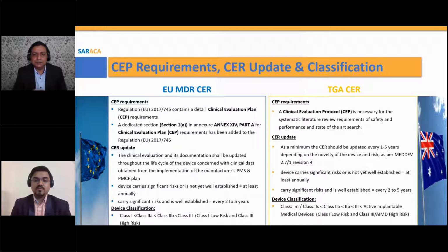Over to you, Sam. Yeah, I'd like to just follow up a little bit on risk. As I said earlier, risk is making its way into everything. And the risk analysis that you do for your device is to be included in the technical documentation, whether it be here in the United States, in the EU, in the TGA, or whatever jurisdiction you're going to market in. Risk analysis is no longer something that you do once during your design phase and then put up on a shelf and expect it to be current.